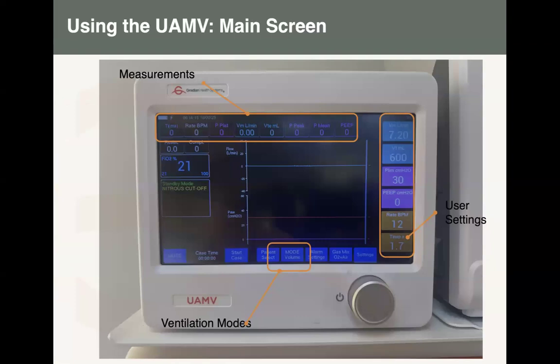So on the main screen of the ventilator, there are parameters which are the ones we set. You are either in the volume mode or in the pressure mode. This column here, the user setting, will have different parameters for you to set depending on the mode you're using. Basically, this side is for the ones you are setting, things like the respiratory rate, pressure limit, and tidal volume, of course when you're in the volume control mode. When you're in the pressure control mode, you set the pressure and other things.